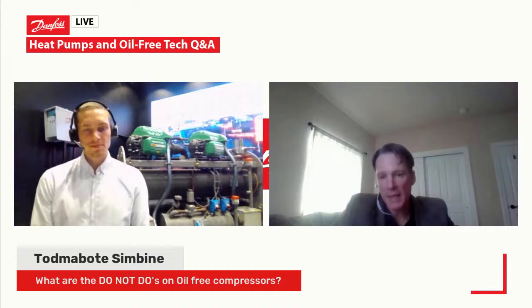Do not operate outside the boundaries. Tying this back to the heat pump systems, we're trying to expand the capability of the compressors to operate in higher temperature applications, keeping in mind that you lose about 1.5% efficiency with every 1K increase in differential temperature. We're going to push the maximum hot water temperature capability of these compressors up to around 75°C by the end of this year.